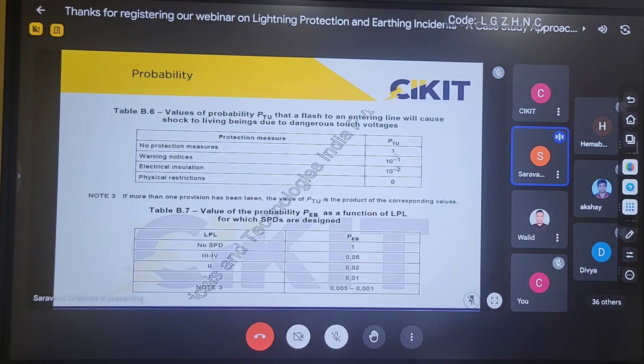Next, if I have electronic equipment, the damage to the electronic equipment can be controlled by installing surge protection devices. Based upon the level of protection, the damage also will be reduced. If there is no SPD, then the value of PEB will be 1. If I have an SPD at level 3 or 4, the value will be 0.05. So observe closely, from 1 it is reducing to 0.05. And if I have lightning protection level 1, then the value is still reducing to 0.01, which is 1 by 100. So by installing the SPD at level 1, I am reducing the risk 100 times.